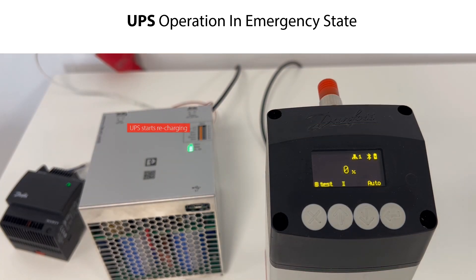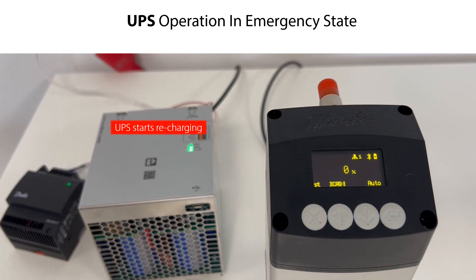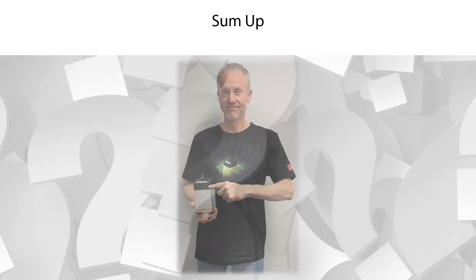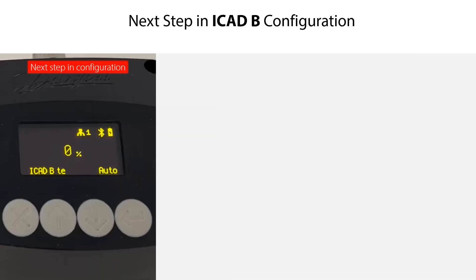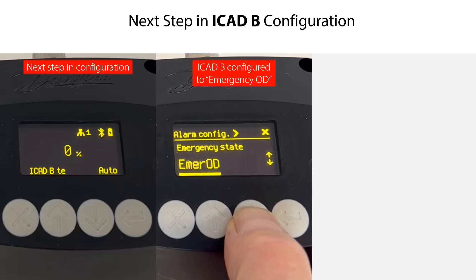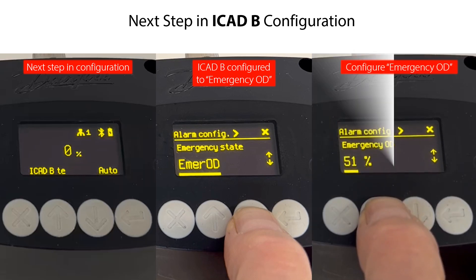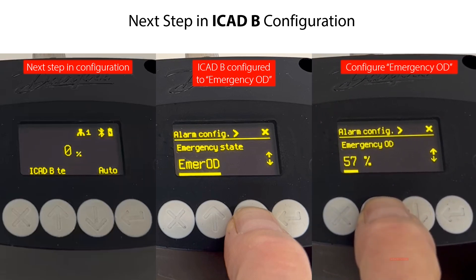You have now seen demonstrated how to configure the UPS emergency state in the ICAD-B, so that you know how to select the needed valve position during a power failure. This will efficiently support you in doing a correct UPS setup and ensure a correct and safe system operation. The ICAD-B is now ready for the next step. Please note that if you have configured the ICAD-B to activate the valve position Emergency OD during a power failure, then you also need to configure the UPS emergency opening degree in the ICAD-B.